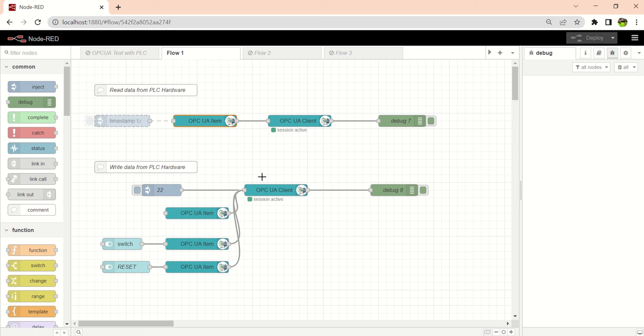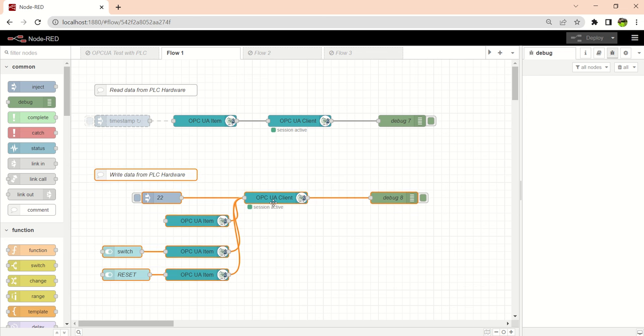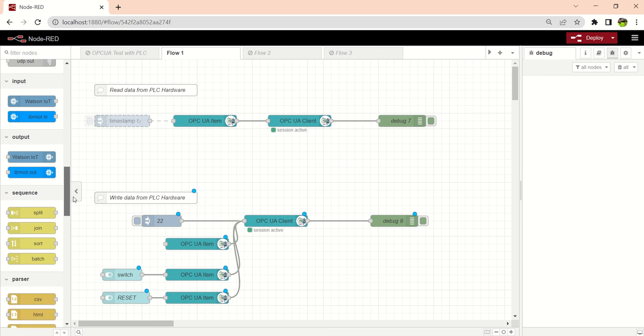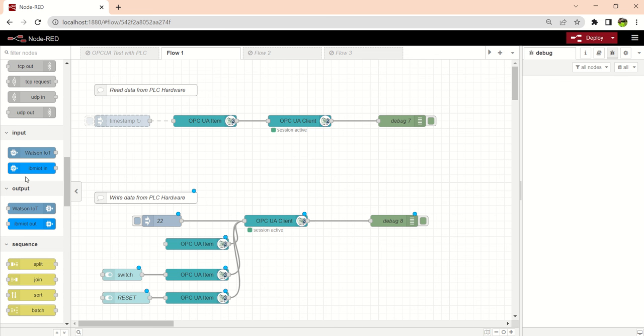From what we did in previous videos, we've got some connections here from the PLC. We're using an OPC protocol to create that. So I want to read this data in, and then I eventually want to push this data. We've used OPC to read the data in, and then we're going to push the data up to the IBM Watson account. We're going to use some of the IBM libraries to connect us to our specific IBM Watson table that we're looking for. That fundamentally uses an MQTT protocol that will get us up there. So this will be quite interesting.